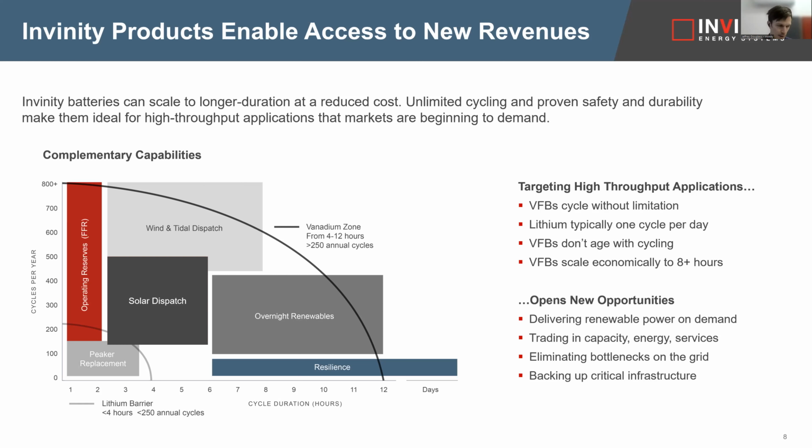So it's keeping along the lines of the same core technology, but optimizing the way the power is generated, and the path from redox difference to a high voltage AC. So focusing on that power transfer chain and optimizing that. That's where a lot of the losses are going to come out. Some of the efficiency is coming from auxiliary losses, right? Auxiliary consumption is less well attended to, and something else that comes into broader project economics or product use case specific stuff. The majority of it is coming from the power chain, charging and discharging, and a small portion from aux consumption reduction.